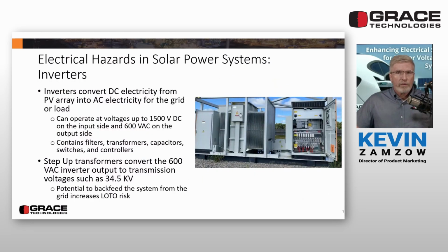Utility scale and solar power inverters are fed by many combiner boxes at up to 1,500 volts DC on the input side and invert the power to up to 600 volts AC on the output, which is then stepped up to transmission voltages, for example, 34.5 kV in this image. Exposure to high power on both the input and output sides during the absence of voltage testing for lockout tagout for maintenance can be mitigated through panel test points for the absence of voltage testing. Note that push button style AVTs are not rated for over 1,000 volts and may not be used on the DC input side if the voltage is over 1,000 volts.